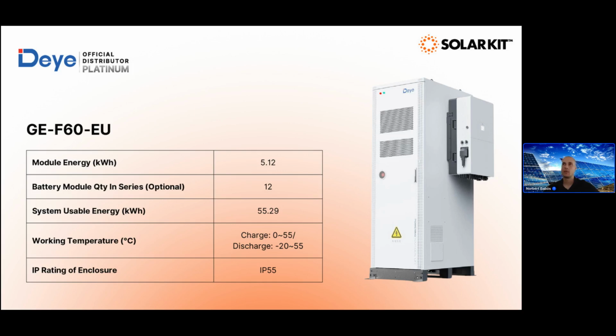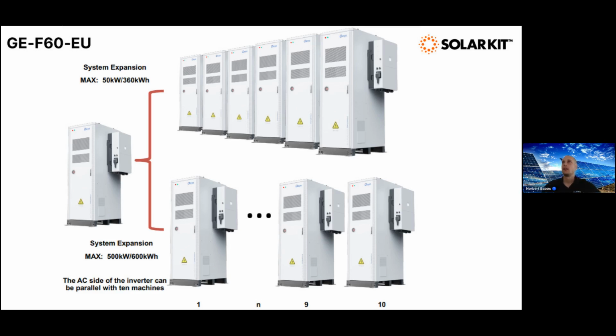Working temperature is the same as for all kinds of Deye batteries: charging from 0 to 55 and discharging from -20 to 55. It's IP55, so you can place it outside. And here are the expansions of one single inverter on the top side. When you have just one inverter connected to the batteries and it's enough for you for the AC power, you can connect 6 pieces. So you would have 50 kilowatt AC power and 360 kilowatt hour battery capacity maximum.